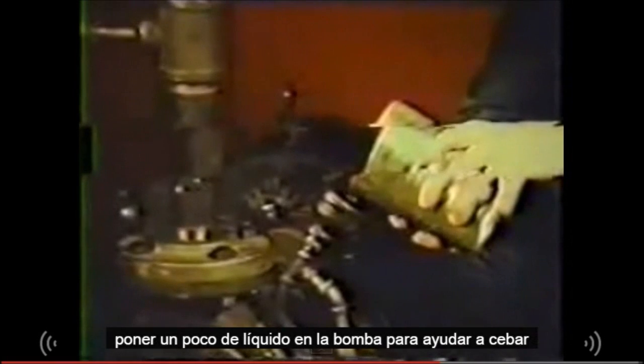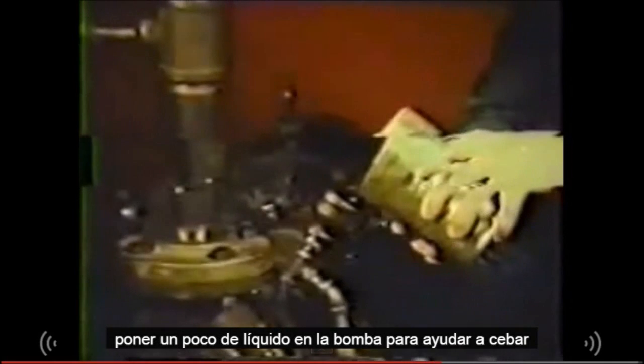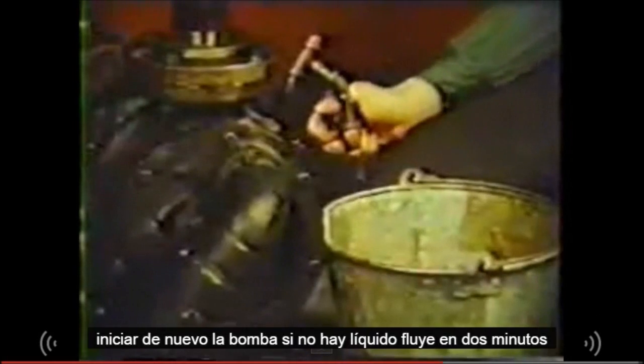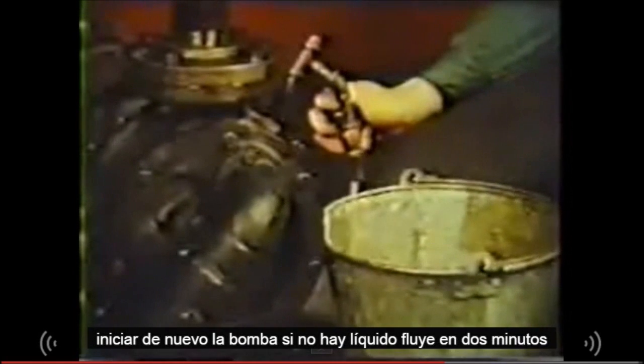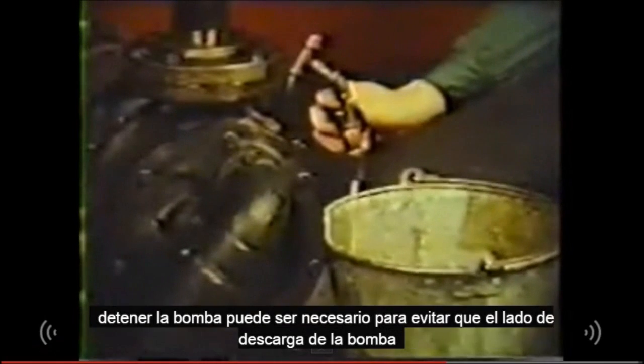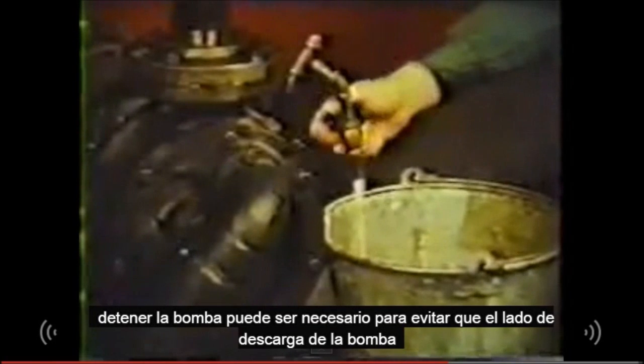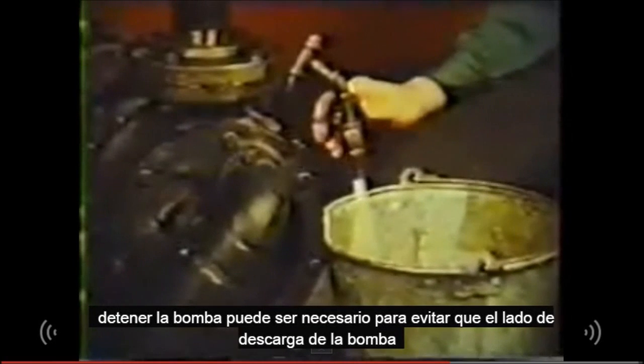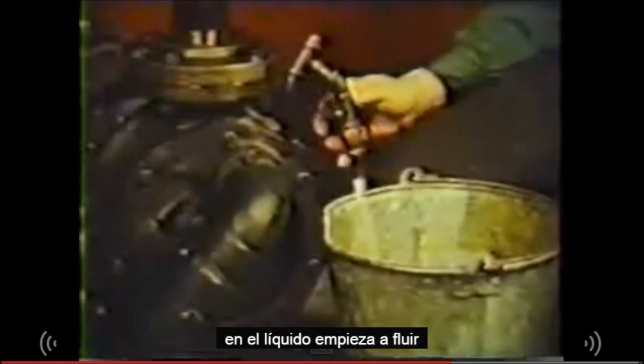Review the steps just outlined. If everything appears in order, put some liquid in the pump to help it prime. Start the pump again. If no liquid is flowing within 2 minutes, stop the pump. It may be necessary to vent the discharge side of the pump until liquid begins to flow.